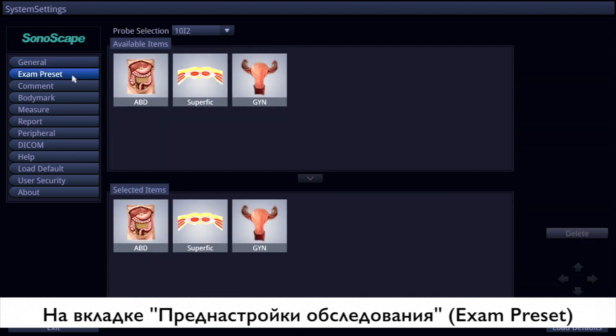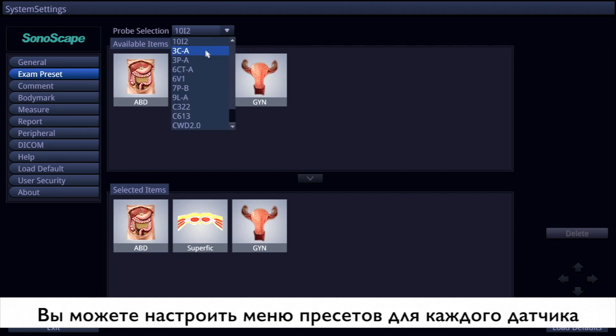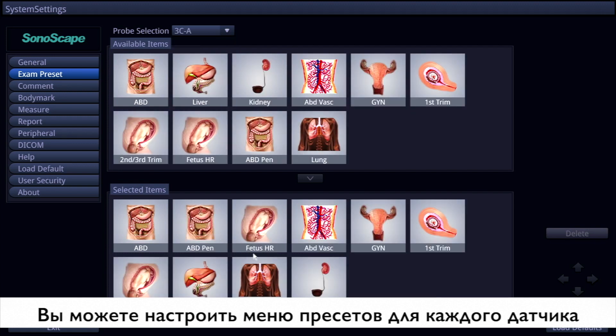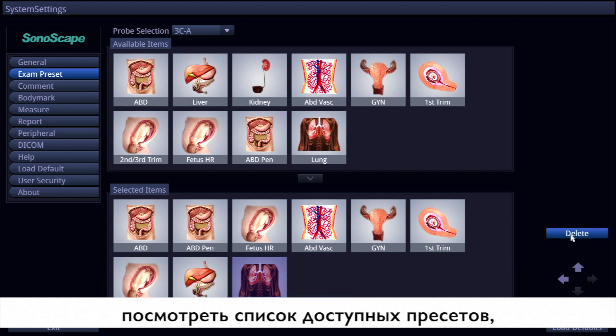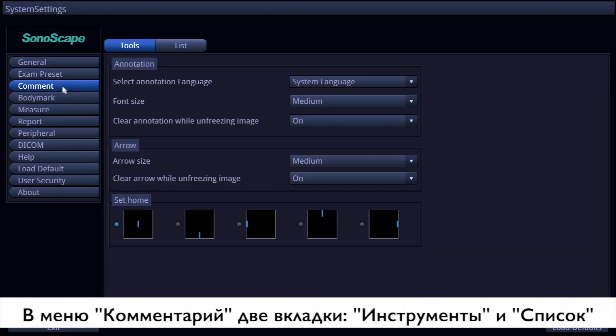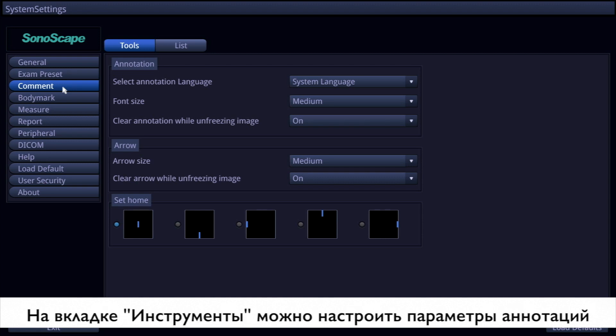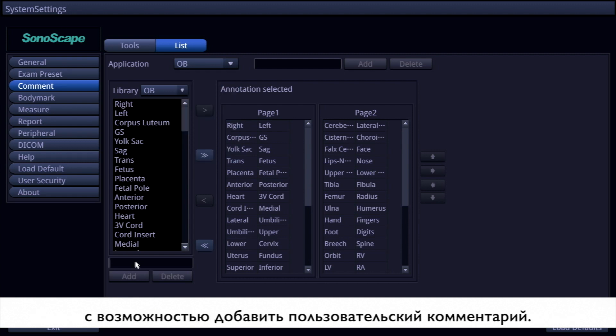Next, let's go to the exam preset item. You need to choose the probe you want to change the preset for. The presets shown on the probe interface are listed in the selected item column. They can be rearranged by the arrows and buttons on the bottom right. You can also add exam presets into the selected items. There are two pages under comment items: tools and lists. On the tools page, you can customize the annotation elements. On the list page, commonly used comments in different applications are listed.